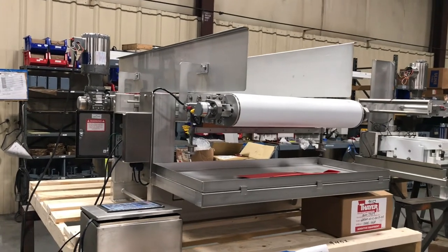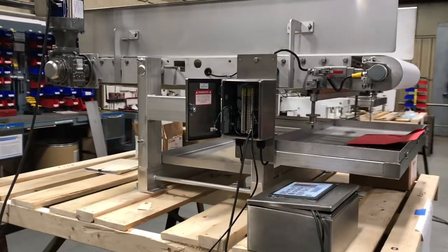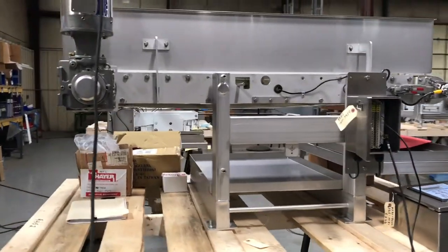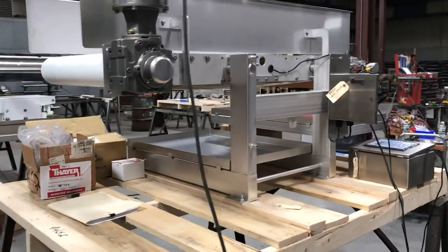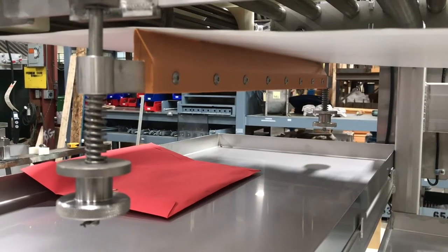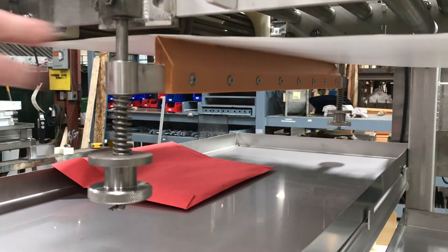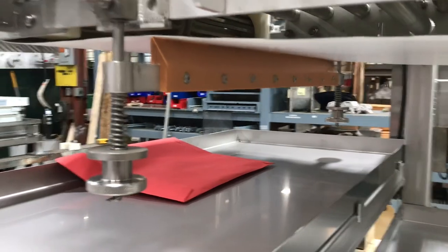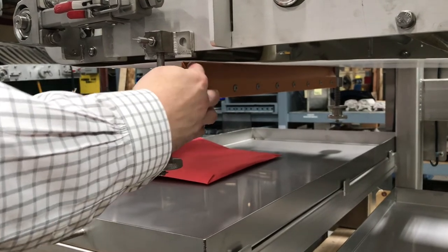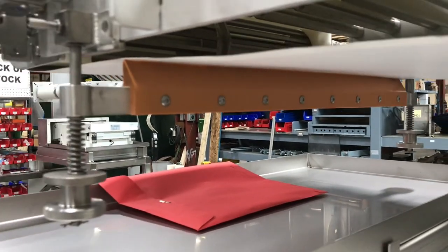Here's another model MWF OS weigh belt that will be measuring the rate of flow of cooked potatoes in a process that makes various chilled potato, chicken, and egg-based salad products for restaurant and food service needs, as well as custom formulated and private label products. This weigh belt features a spring-loaded belt cleaner that effectively prevents starch and other films from building up on the belt surface. The dual durometer belt cleaner blade combines a rigid portion that accommodates load pressures with a softer portion that provides a resilient edge that minimizes stress on the belt splice and reduces drag, extending belt life.